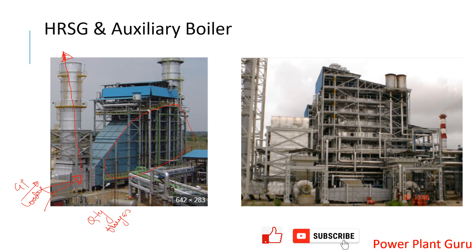On the right side you can see the auxiliary boiler, also called a utility boiler. In this boiler there are no hot gases or waste heat sources available — it is based on the requirement of the process or steam. Most of the cases you will find a forced draft system, otherwise a balanced draft system. With a forced or balanced draft system, the operator has the liberty to maintain the draft, excess O2, and air-to-fuel ratio — everything is in the operator's control.